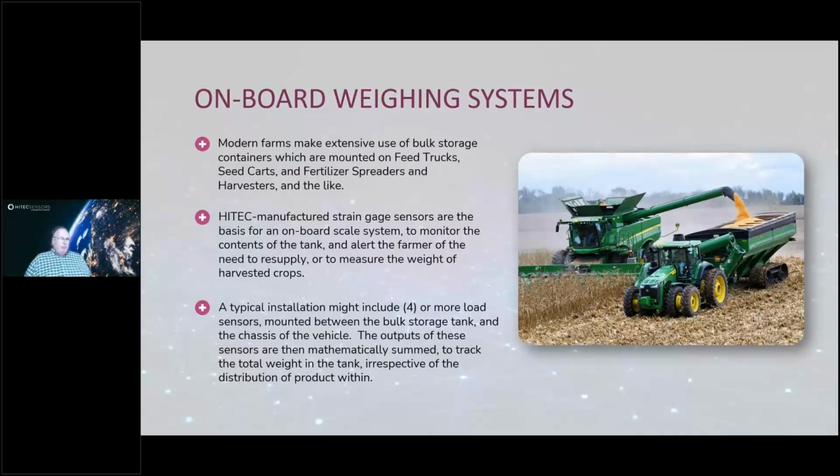The installation might be a load cell mounted between the tank and frame of the vehicle, or alternately, it could take the form of a cantilevered pin that would serve as the axle for a cart. So essentially, think of an instrumented axle spindle that is instrumented to measure how much load is applied in the tank or storage bin.